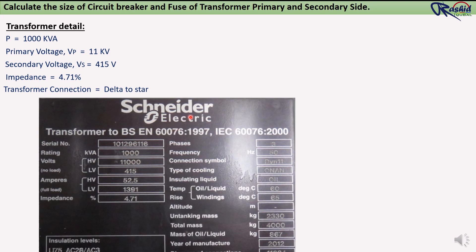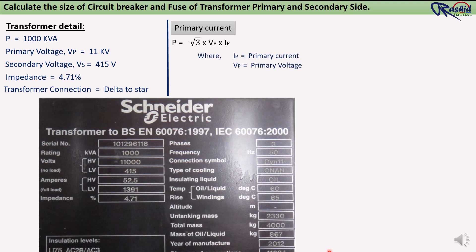Now first we need to find out the full load current of this transformer at the primary and secondary side. Although the current rating is already written on the nameplate, still for your understanding we will calculate primary and secondary current here. The formula is P = √3 × Vp × Ip, where Ip is the primary current and Vp is the primary voltage.